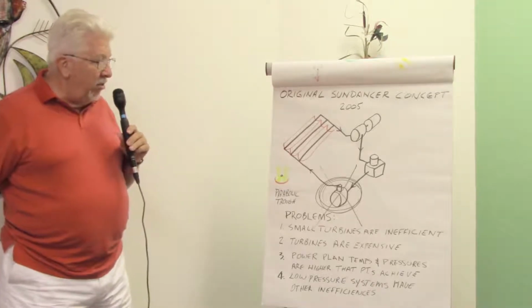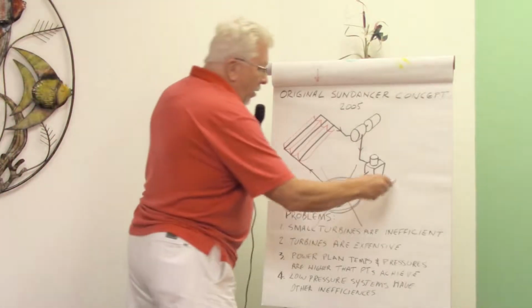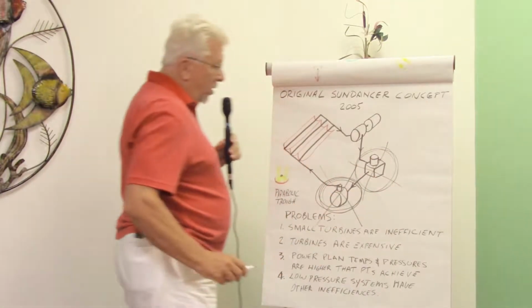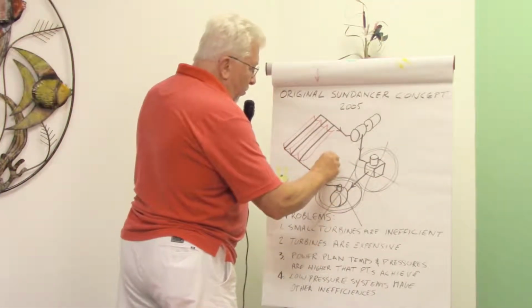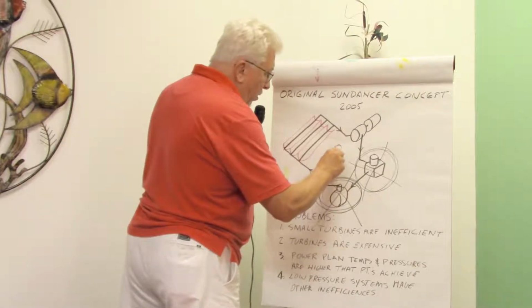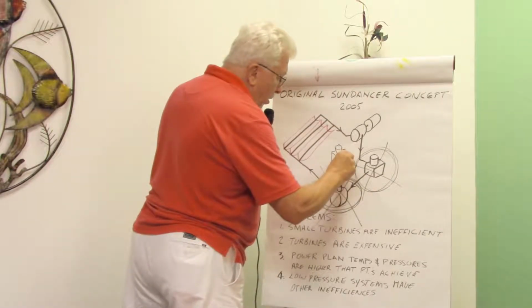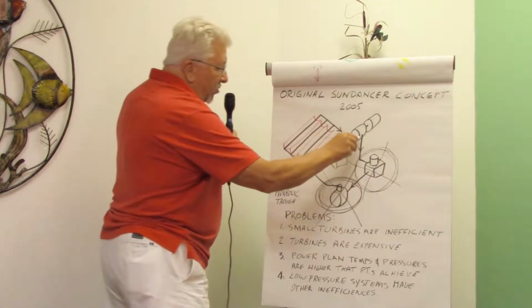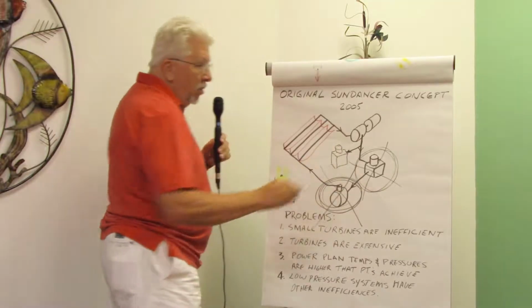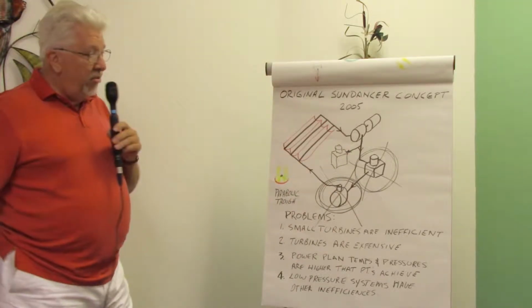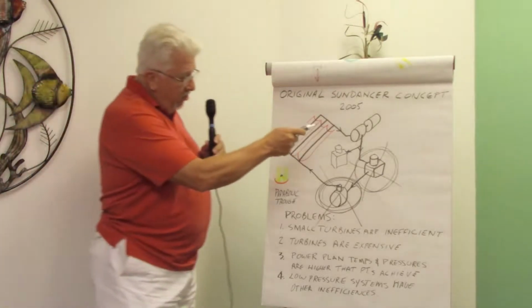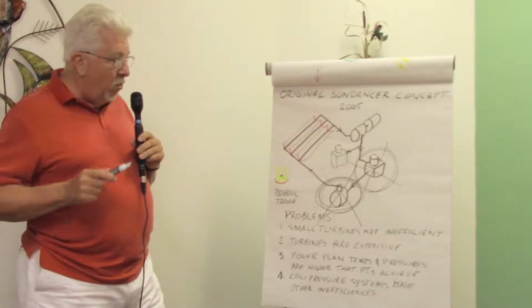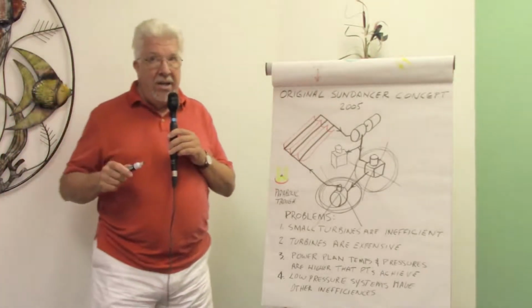okay? Not using a boiler feed pump, eliminating the condenser altogether, and creating a special system that was designed to take the turbine exhaust that has still got some steam and some liquid in it, because the low pressure system that we're using, part of the way that you make a low pressure system more efficient is to use what's known as a semi-condensing turbine.